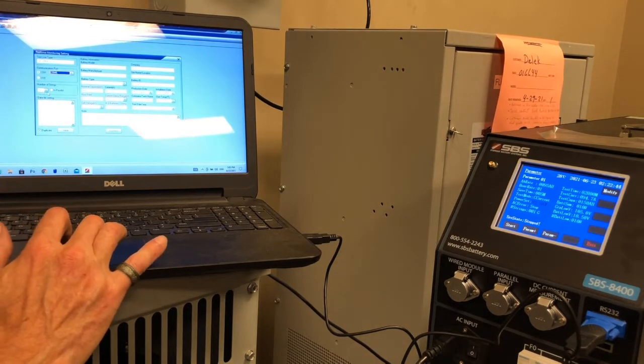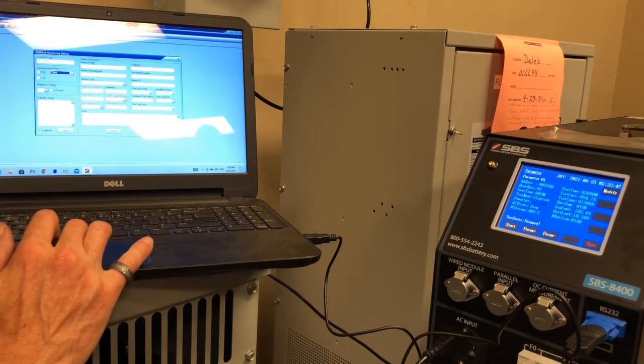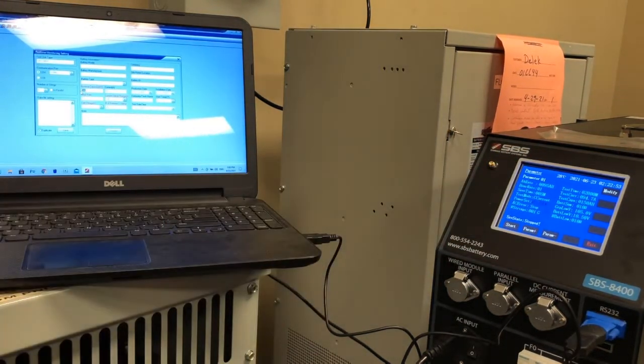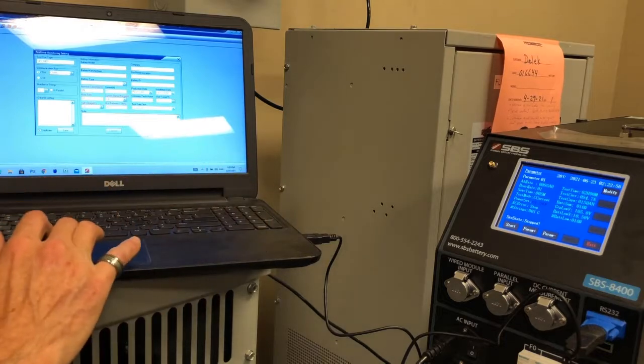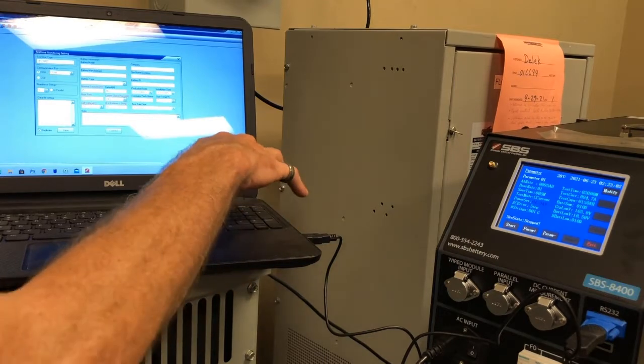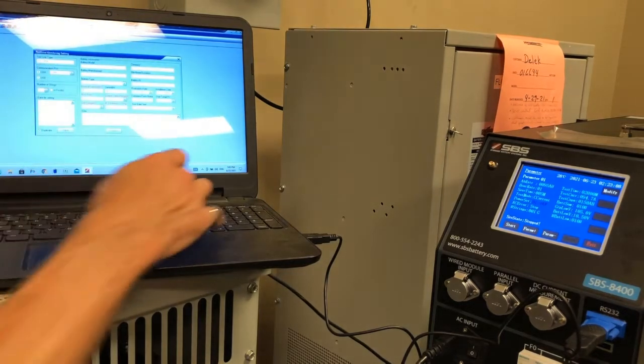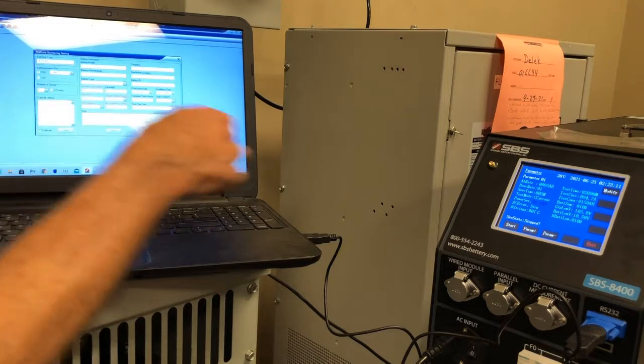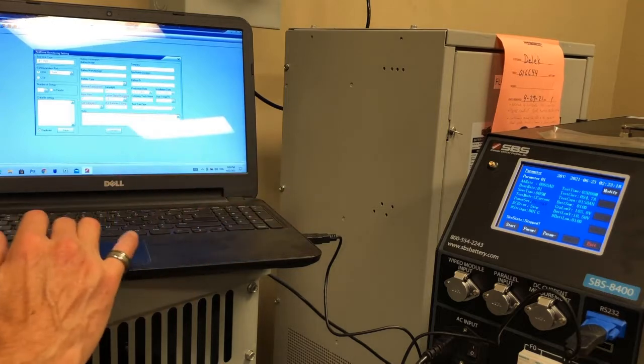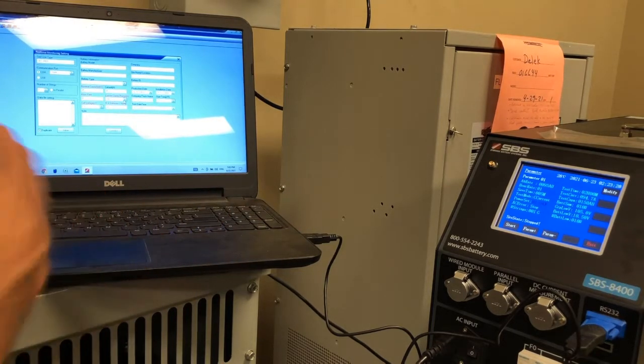Okay. Number of strings, 1, right, not in parallel. My nominal capacity, 95 amp hours, right? Yep. My current, 94.5 amps, 94.7 amps. It won't take a decimal point, so I'm just going to put that in as the same 95 that I rounded off to. My hour rate is a 1 hour rate. My current clamp range is NA because I'm not using an external current clamp.